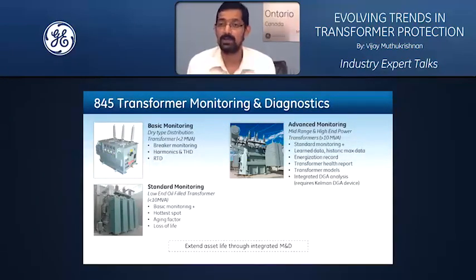It's one example. Energization record is another nice functionality, where the protection relay can capture the first 10 cycles of raw current samples whenever a transformer is energized, and use them to calculate things like maximum inrush current. It can also capture voltage samples and give you the voltage dip experienced by the system when you energize the transformer, and so on. That's again a very accurate way of characterizing energization behavior over a period of time.